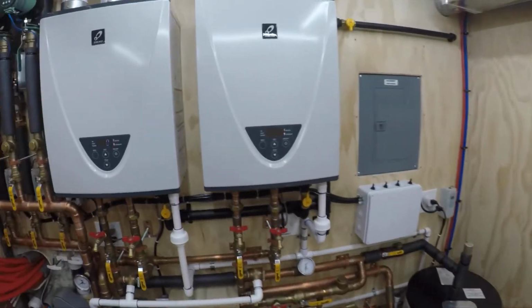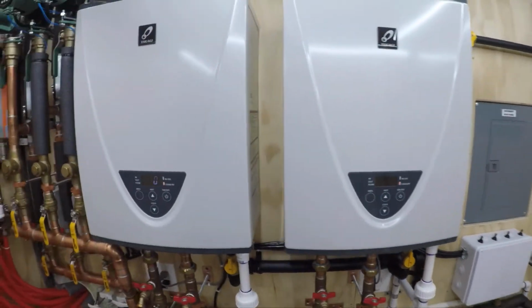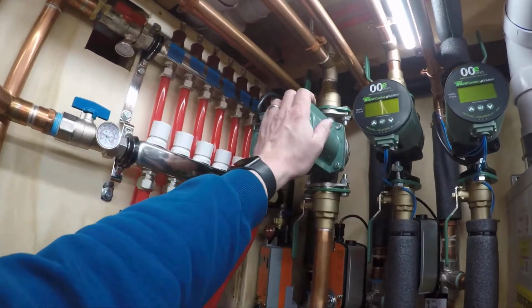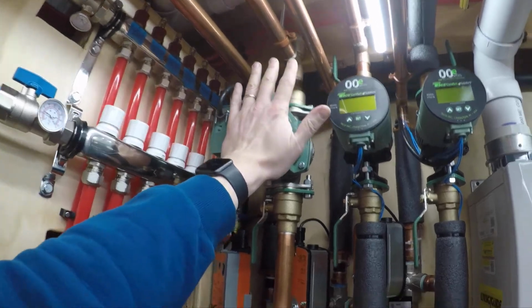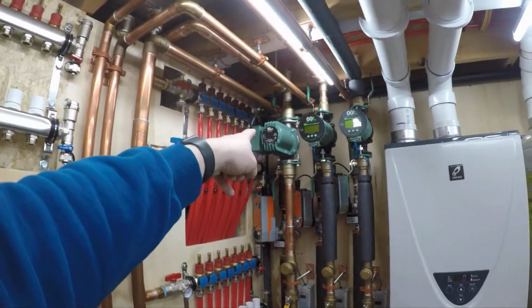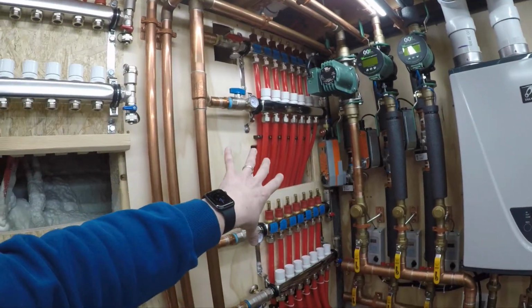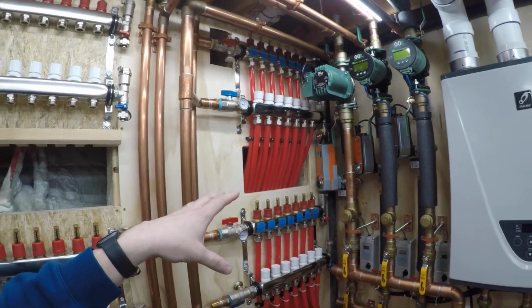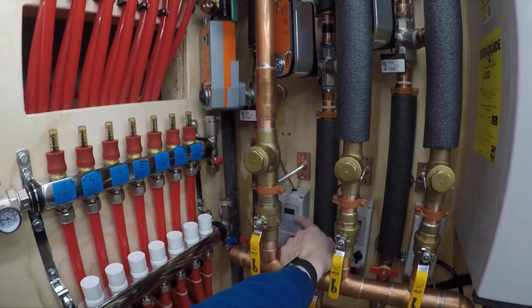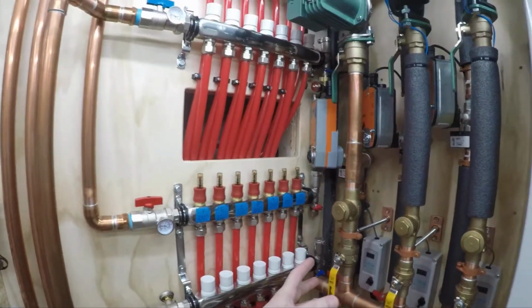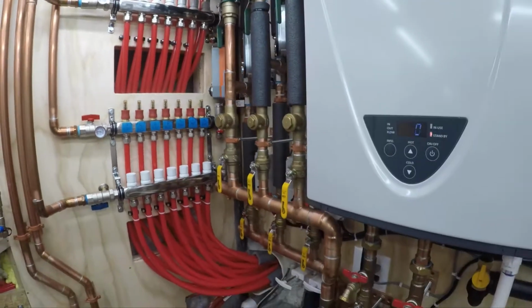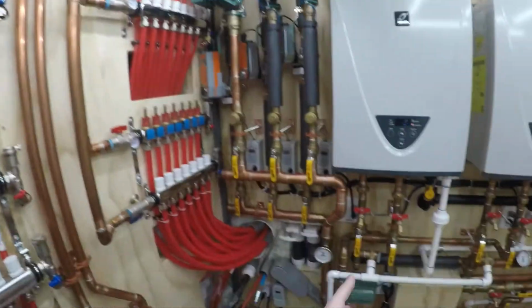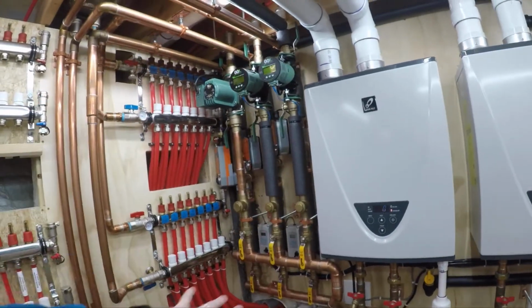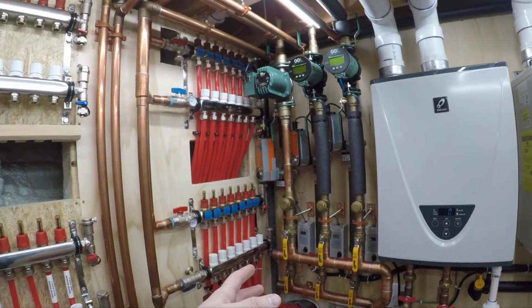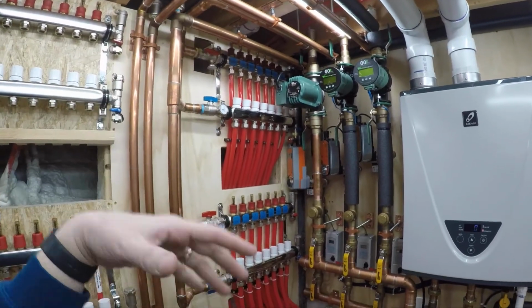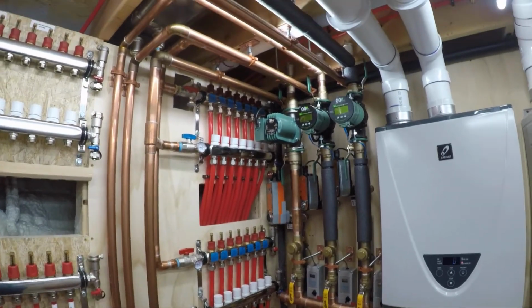Now the Snowmelt, I turn on and off also from my smartphone. It does a very similar thing. It turns on this pump, and this pump stays on all the time as long as the Snowmelt is on. That Taco 13 is pumping glycol through the driveway. Okay? Same exact concept. When that glycol, and right now I have the aquastat set to 80 degrees. So when the return glycol coming back from the driveway gets to 80 degrees, it shuts off the primary pump. Okay? But the driveway's still circulating, and I have that on a 15-degree differential right now. So it pumps that 80-degree glycol round and round until it loses heat. It drops to 79, 78, 77.